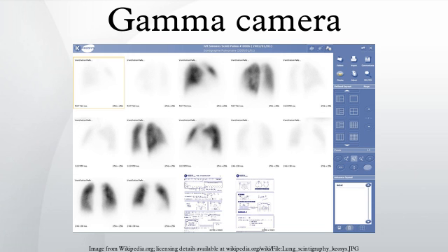Other methods of image localization have been proposed and tested. However, none have entered widespread routine clinical use. The best current camera system designs can differentiate two separate point sources of gamma photons located a minimum of 1.8 cm apart, at 5 cm away from the camera face.